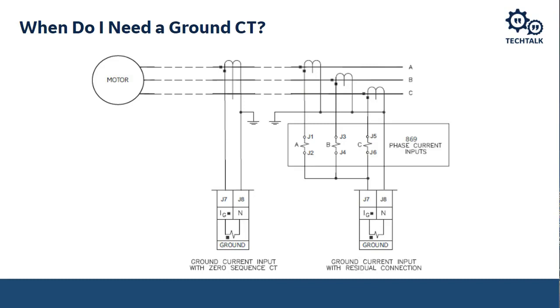So when I'm using this type of connection for ground fault detection, I've got to make sure my ground fault is going to be pretty high, and the accuracy is not going to be a concern. However, as we talked about, when we're engineering low impedance, when we engineer the ground fault current, we want it to be low, so that in our residual connection, we might not be able to detect it reliably. So we use what we call a ground current CT with a zero sequence connection.